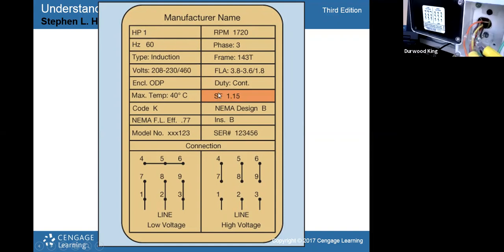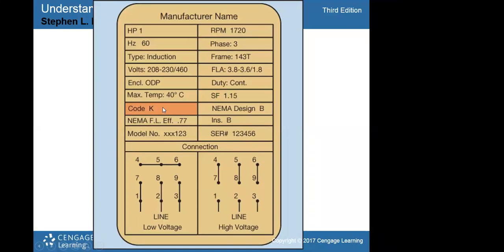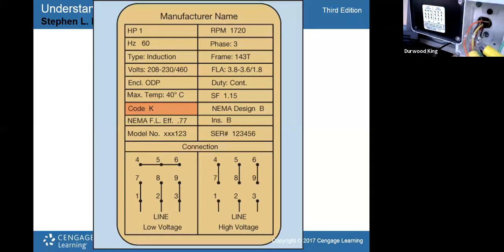Okay, your code letter is referring to locked rotor current. When the motor starts up from a dead still, they call that locked rotor current. So K is a code that can help you calculate what the starting amps would be for the motor if you wanted to know that. You can look on pages 364 and 365, and it gets into calculating.